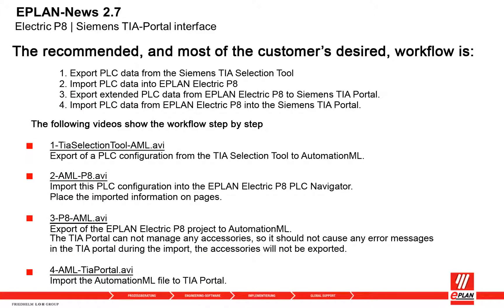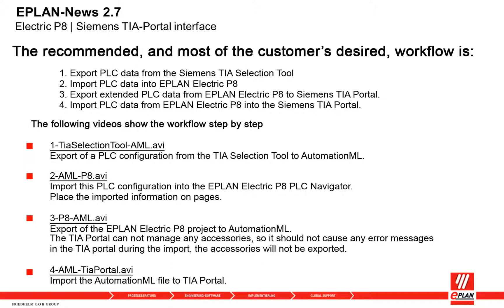The recommended workflow is: 1. Export PLC data from the Siemens TIA Selection Tool. 2. Import PLC data into ePlan Electric P8. 3. Export extended PLC data from ePlan Electric P8 to Siemens TIA Portal. 4. Import PLC data from ePlan Electric P8 into the Siemens TIA Portal. The following videos show the workflow step by step.